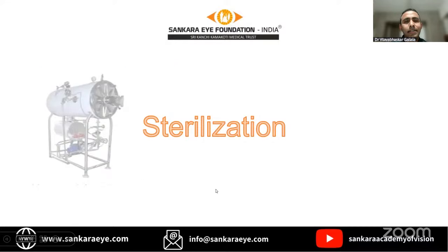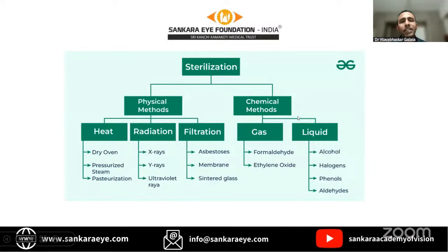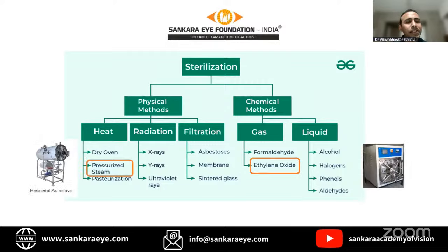Finally, once the set is ready, we'll go for the sterilization proper. There are different types of sterilization techniques available: physical methods and chemical methods. In physical methods, there is heat sterilization, radiation, and filtration. In chemical methods, gas and liquids. I'm not going to talk about all methods right now. The most commonly used and effective sterilization technique in ophthalmology is pressurized steam, that is autoclave sterilization. Another one is gas sterilization, that is ethylene oxide sterilization, for instruments which are heat sensitive.